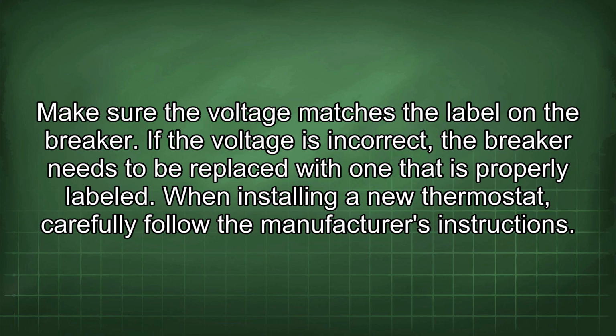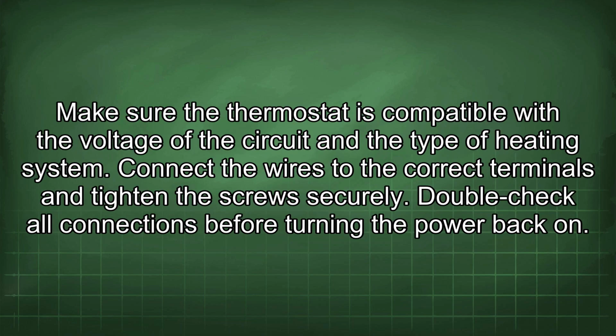Make sure the voltage matches the label on the breaker. If the voltage is incorrect, the breaker needs to be replaced with one that is properly labeled. When installing a new thermostat, carefully follow the manufacturer's instructions. Make sure the thermostat is compatible with the voltage of the circuit and the type of heating system. Connect the wires to the correct terminals and tighten the screws securely. Double-check all connections before turning the power back on.